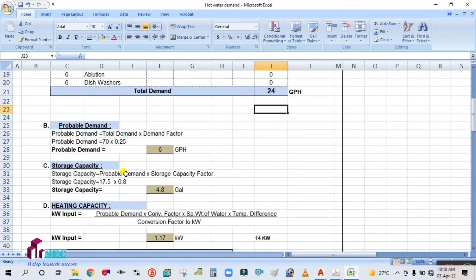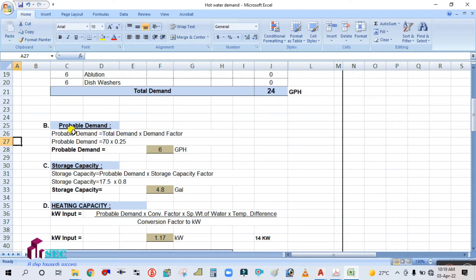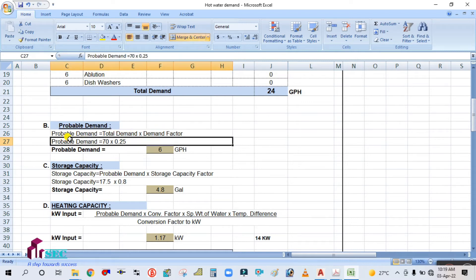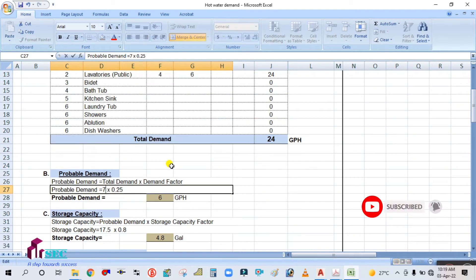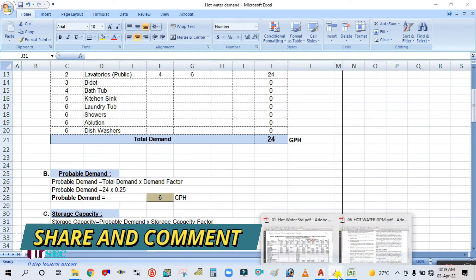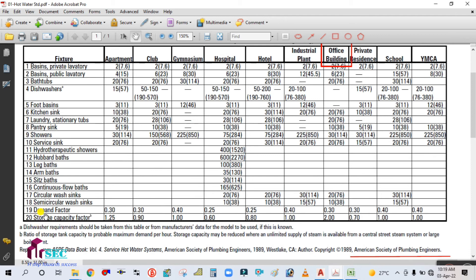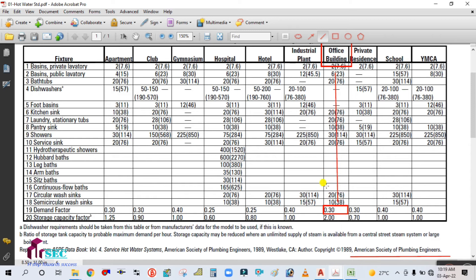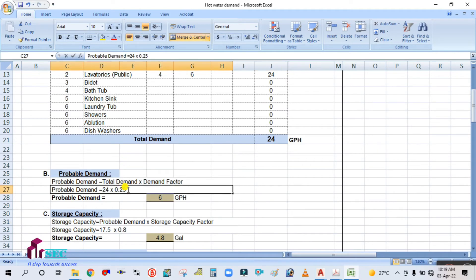To calculate the storage capacity, we need the probable demand and the storage capacity factor. The formula is: Probable Demand = Total Demand × Demand Factor. Total demand is 24 GPH. For the demand factor, go back to the table — serial number 19, demand factor. For office building, the demand factor is 0.30. Change the value to 0.30 in the spreadsheet.